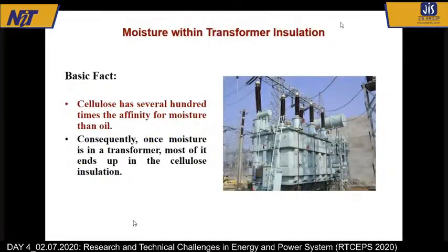Now, if you take the case of a transformer, as I said, moisture will be generated inside this transformer. But then where will this moisture go? By the way, when we teach our students, we tell them that transformer oil is hygroscopic in nature. When you say hygroscopic, we mean that if you keep transformer oil exposed to atmospheric air, it will absorb moisture. But the unfortunate part is that the paper insulation, that means the cellulose, has an affinity for water 100 times more than oil. So inside this transformer, if there is moisture and two materials are trying to attract it, one paper and one oil, and paper's water affinity is 100 times higher, it is quite obvious that most of the moisture will go to the paper insulation and damage it.